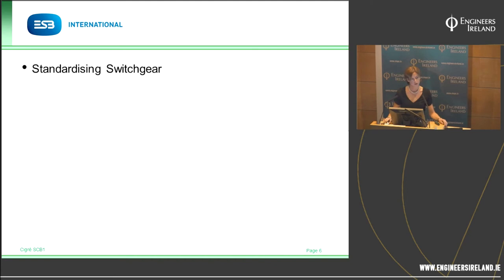We wanted our new stations to be a little bit like those old Siemens stations in that they would all look the same, and not from an aesthetics point of view. Using standard design templates reduces design time and thereby speeds up the project. Our switchgear orders were no longer bespoke. We set up term contracts with the switchgear manufacturers, and we limited ourselves to one or two choices.